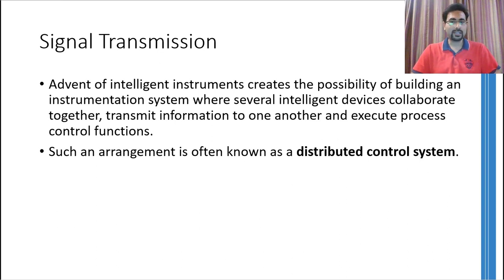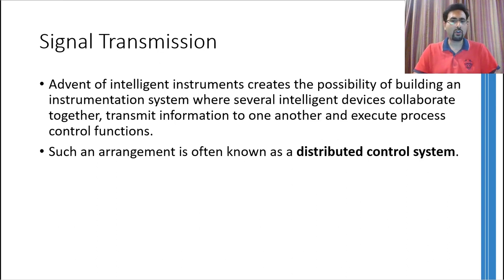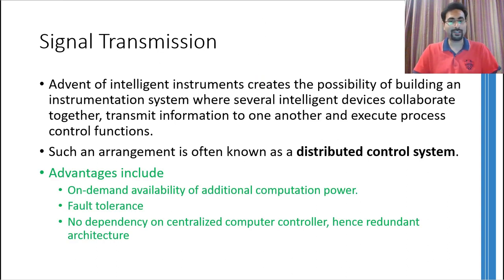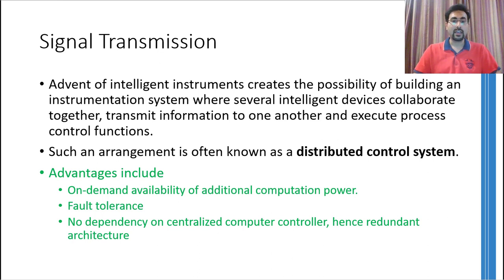Such a scenario is known as a Distributed Control System, or DCS for short. This kind of system doesn't have any central processing unit, but what is happening is that all the devices are performing some kind of processing and they are modifying the signal before routing it to any other device that needs that information. The main advantage of using a Distributed Control System is that you can easily add more computational power into the whole system without disturbing it.